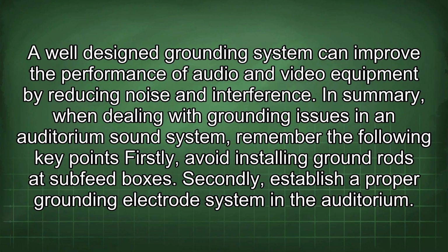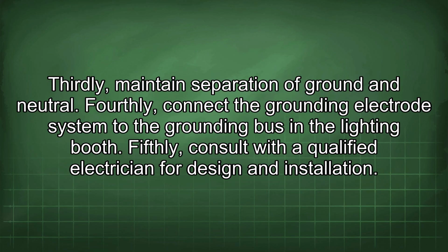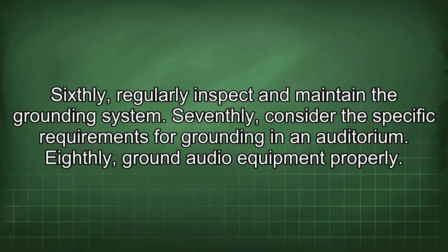In summary, when dealing with grounding issues in an auditorium sound system, remember the following key points. Firstly, avoid installing ground rods at subfeed boxes. Secondly, establish a proper grounding electrode system in the auditorium. Thirdly, maintain separation of ground and neutral. Fourthly, connect the grounding electrode system to the grounding bus in the lighting booth. Fifthly, consult with a qualified electrician for design and installation. Sixthly, regularly inspect and maintain the grounding system.